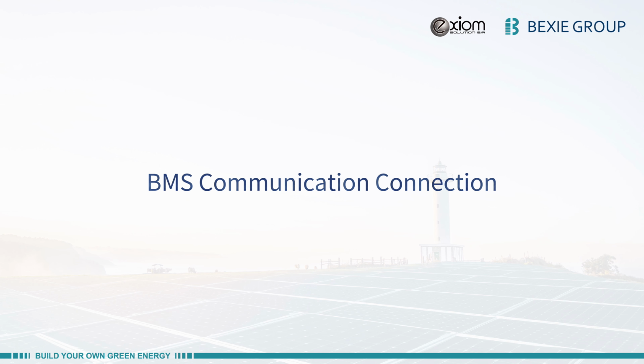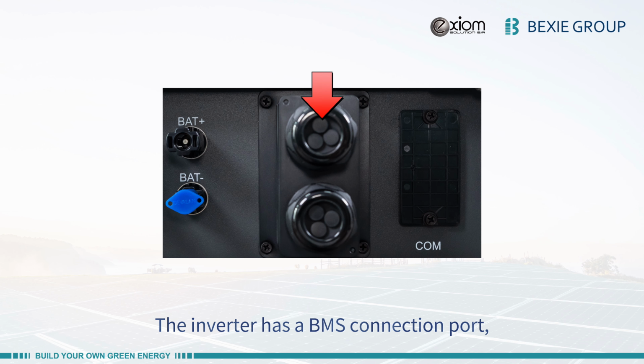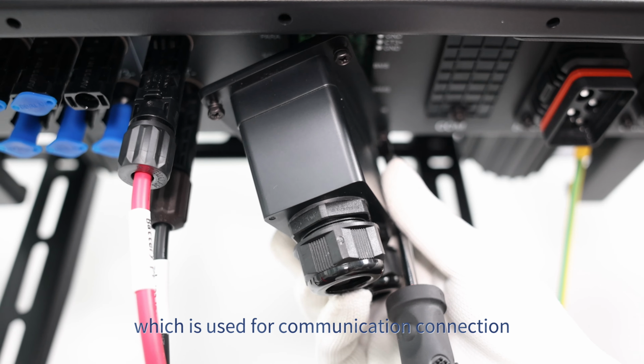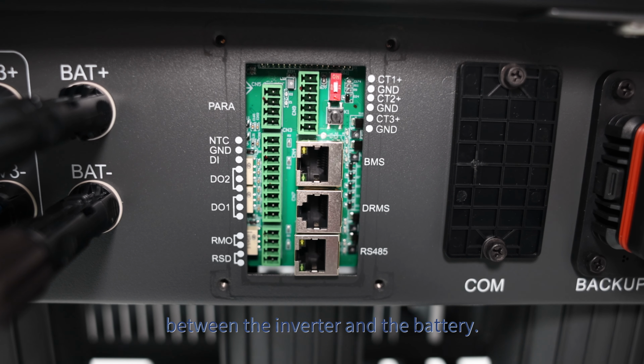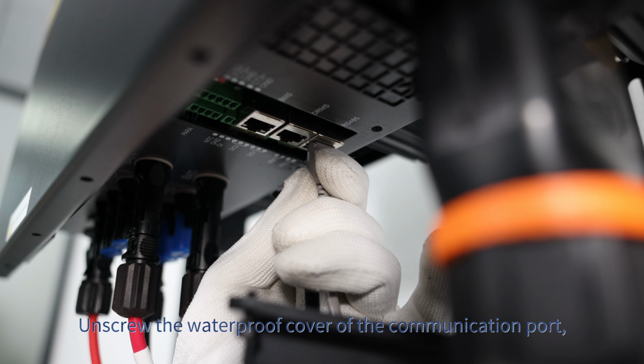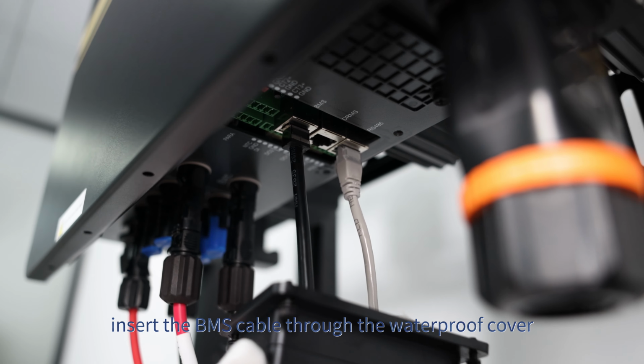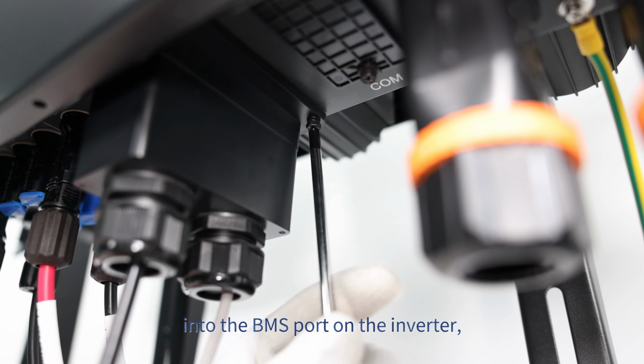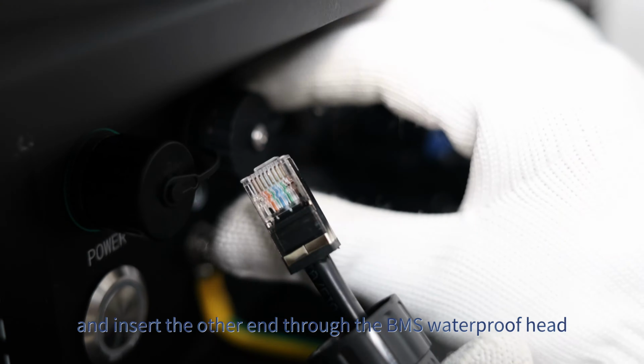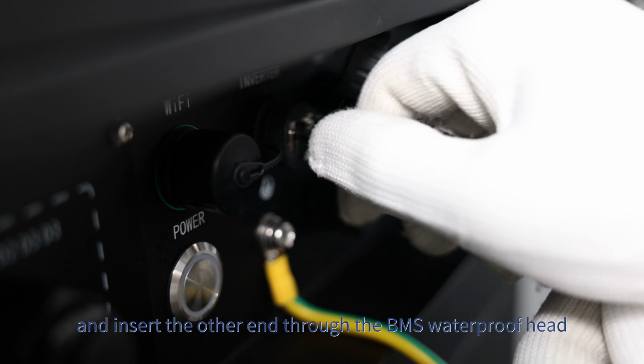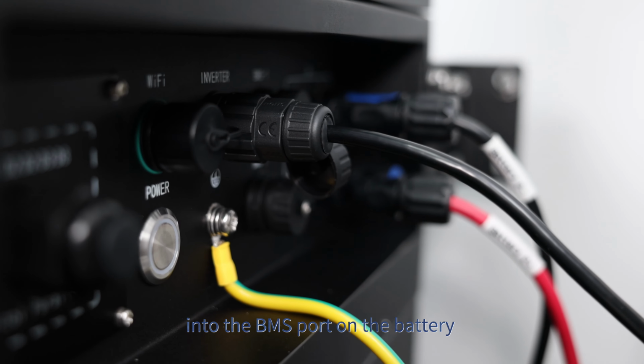BMS communication connection. The inverter has a BMS connection port, which is used for communication connection between the inverter and the battery. Unscrew the waterproof cover of the communication port. Insert the BMS cable through the waterproof cover into the BMS port on the inverter, and insert the other end through the BMS waterproof head into the BMS port on the battery, and tighten it.